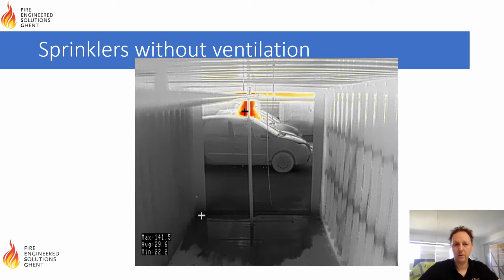Nice to know, it was a sprinkler system dimensioned based on ordinary hazard 2. It wasn't dimensioned based on 12 heads activating simultaneously, but it was dimensioned based on 8 heads activated simultaneously. And still really good results, where during the tests 2 or 3 sprinkler heads activated.